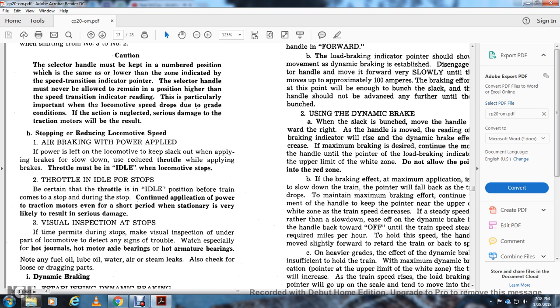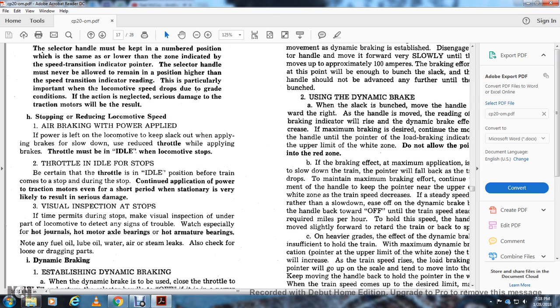Visual inspection at the stop. If time permits, during the stop make a visual inspection of the locomotive for any sign of trouble. Watch especially for hot journals, hot main motor axle bearings, hot armature bearings, and any fuel, lube oil, water, air or steam leaks. Also check for loosening or dragging parts.